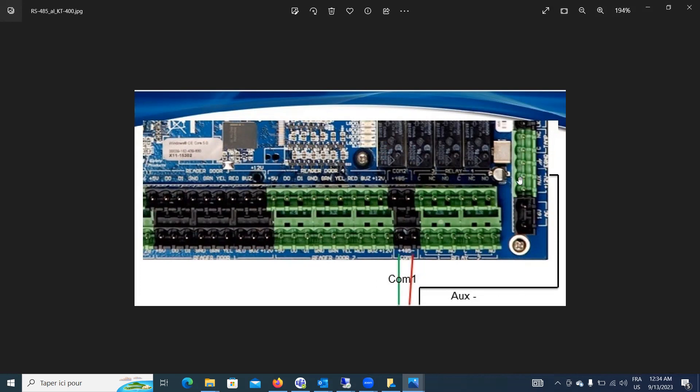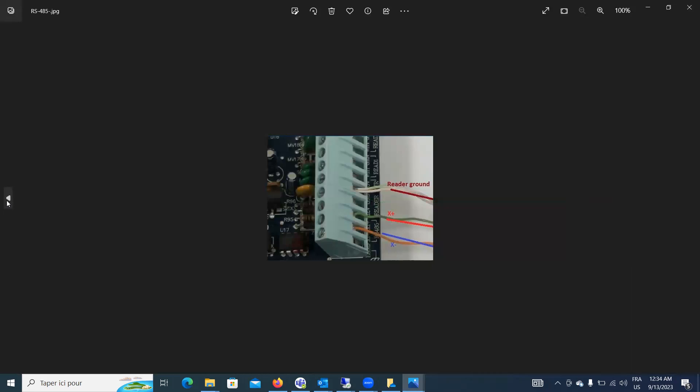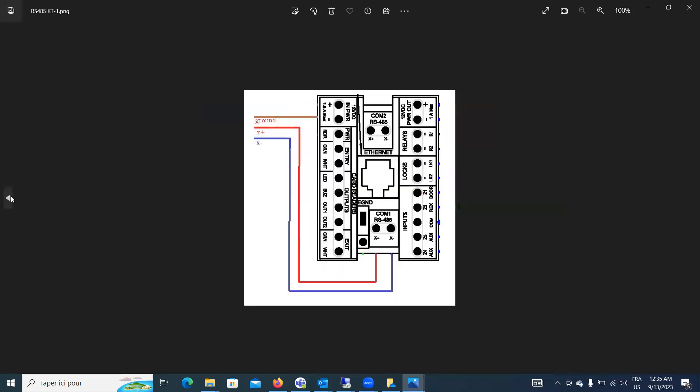So X plus, X minus, and the ground. So based on which controller you have, for KT-400, you see that's the aux negative. Then this one is the KT-300 or 315. So you have X plus, X minus, X plus. You have the ground. That's the reader ground, the same ground where you connect your reader. It's the same ground you use for the reader cable, I mean ground. That's the one for the communication. I bring your attention to that because there is the electrical ground. Now, after that, for example, if you keep going, if you're going to keep adding KT-300, KT-315, same principle. You got X plus to X plus, X minus to X minus, and the ground to ground. Okay?